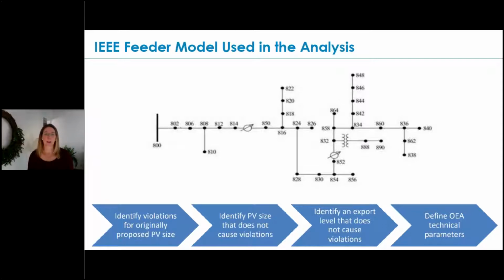We used an IEEE feeder that's open source, and the data is all open source. We chose a representative solar generation profile and a representative load profile from a residential feeder, just to demonstrate the methodology that could be used to develop these operating parameters. So we first identified the violations using an 8760 time series simulation in OpenDSS Direct.